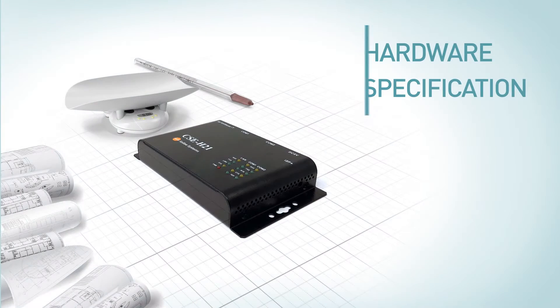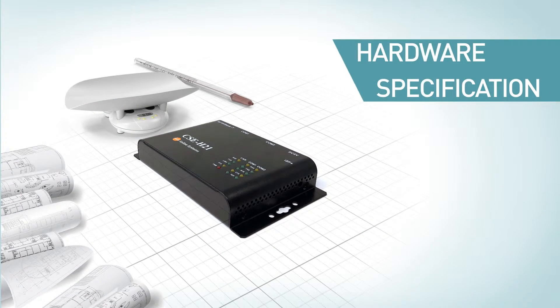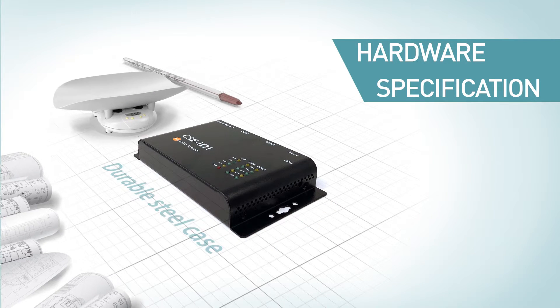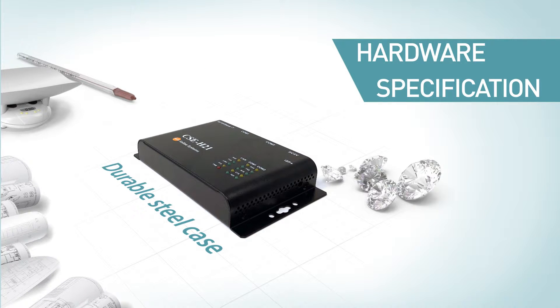Let's look at hardware specifications. The size of CSE-H21 is 158mm in length, 90mm in width, 24mm in height, with 340g. Its operation temperature range is from negative 40 degrees Celsius to 70 degrees Celsius, which is suitable for an industrial environment with its durable steel case.